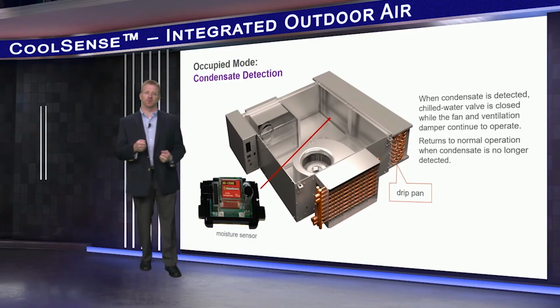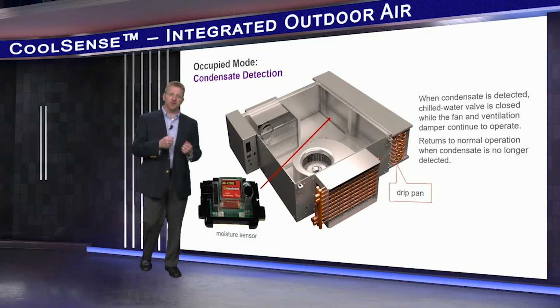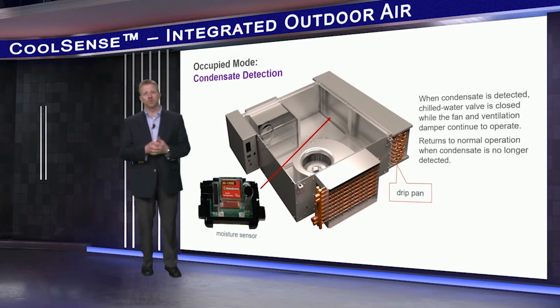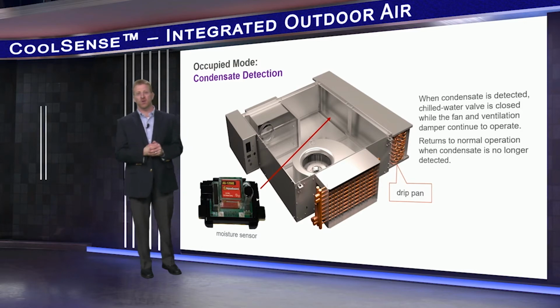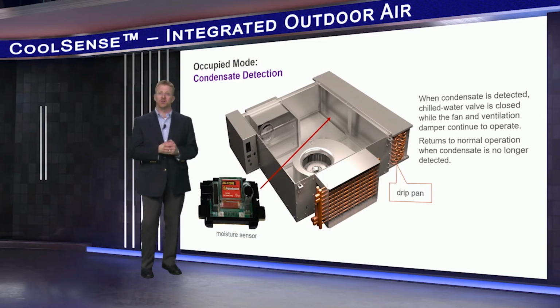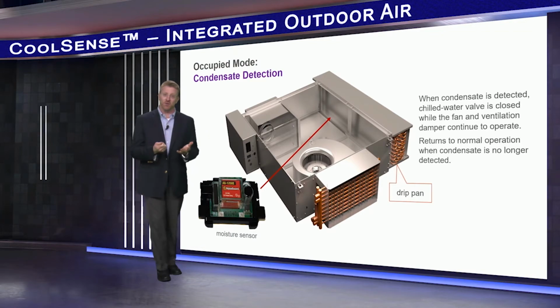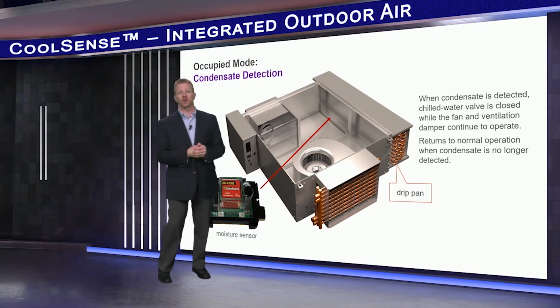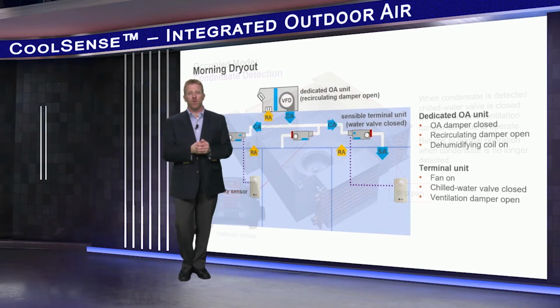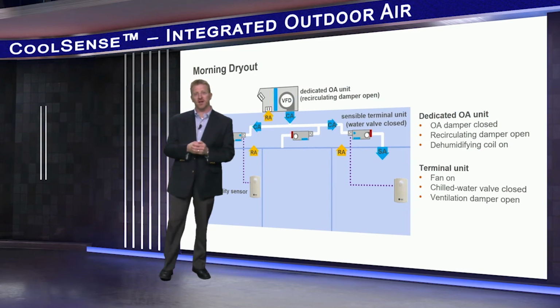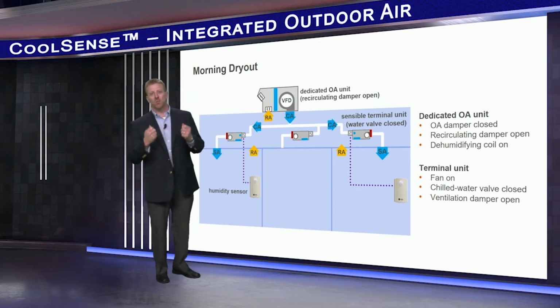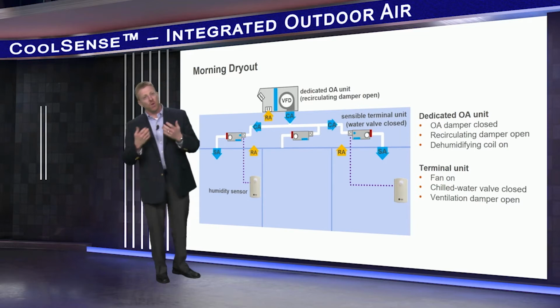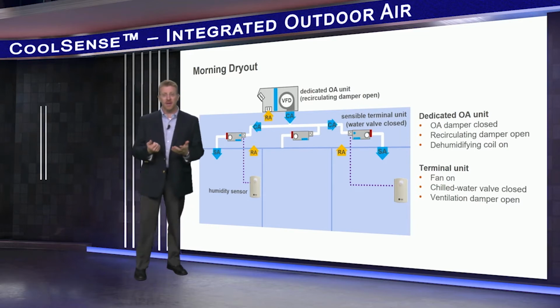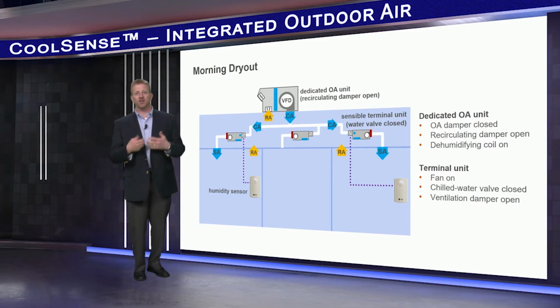At the core of the system is that CoolSense integrates ventilation control into the zone-level cooling and heating terminals, thus providing individualized comfort to each zone while minimizing the energy used for ventilation, a key outcome for designers looking toward net zero energy buildings. Before we move on, one more concept related to condensation is a mode we call morning dryout. While we did not invent the term, it's a new one for many. And to help explain, I start with a familiar phrase, morning warm-up.